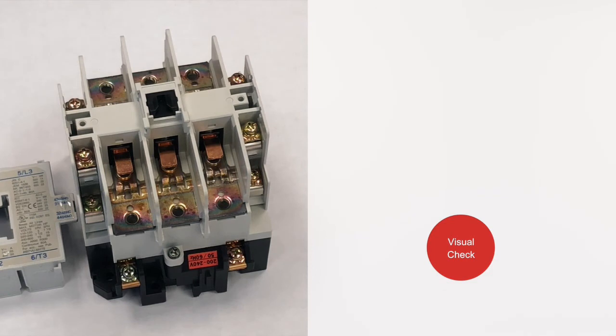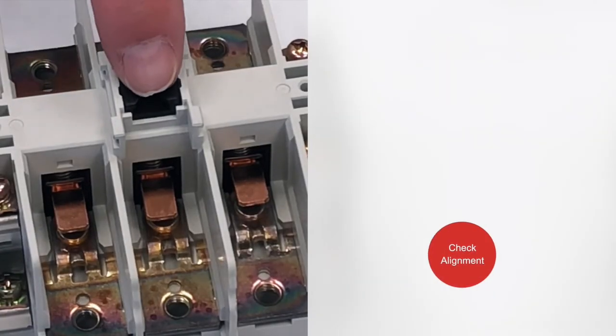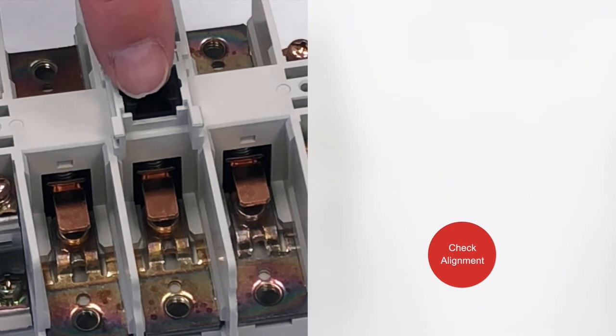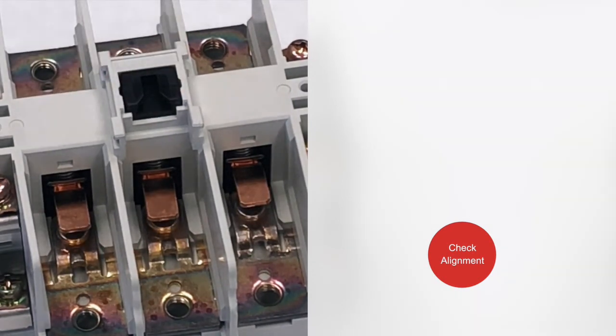Contactors are designed to be normally open or normally closed. This unit is NO, or normally open. You can push down on the movable contact holders to check the alignment as it mates with the stationary contacts. There should be as much contact as possible.